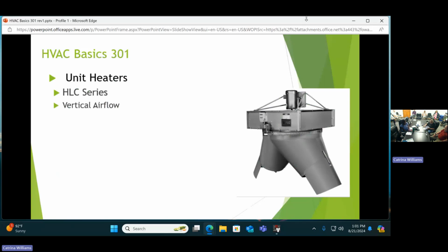You need a category. See, this is really a little bit misleading because there's no heater here. This is just a circulator. Listen to our air turnover units. We talked about by moving the air, we eliminate stratification. Well, that's what we're doing here in essence, is we're putting this up at the ceiling level, recirculating warm air at the ceiling, and putting it back down to the space where you can use it. Because once that hot air is up at the ceiling, it's of no benefit to you or the workers. It's just going to go up through the roof and you've lost it.